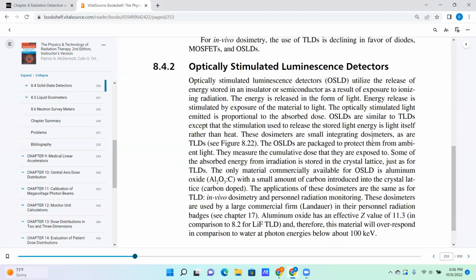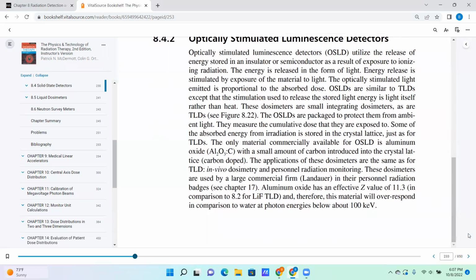These dosimeters are small integrating dosimeters, as are TLDs. The OSLDs are packaged to protect them from ambient light. They measure the cumulative dose they are exposed to. Some of the absorbed energy from radiation is stored in the crystal lattice, just like for TLDs. The only material commercially available is aluminum oxide, with a small amount of carbon introduced into the crystal lattice, or carbon doped. The applications of these dosimeters are the same as for TLDs: in vivo dosimetry and personal radiation monitoring. These dosimeters are used by a large commercial firm, Landauer, in their personnel radiation badges. Aluminum oxide has an effective atomic number of 11.3 in comparison to 8.2 for lithium fluoride. So this material will over-respond in comparison to water at photon energies below 100 keV.